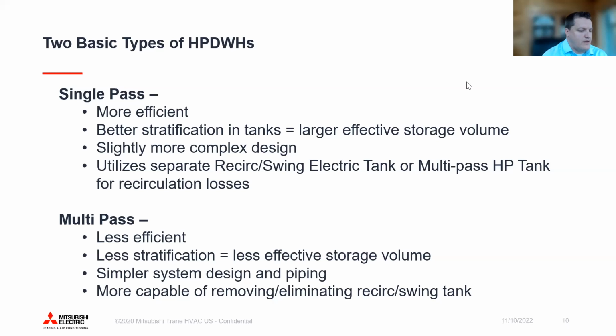When we look at our heat pump offering compared to what the market has today, we offer a single pass heat pump. Basically, that means it takes in domestic cold water from the building's main, and in one pass through our heat exchanger, brings it from maybe 40, 50, or 60 degrees all the way up to your storage temperature of 150 plus or 140 plus. That's one of the main differentiators between our product and others available on the market.